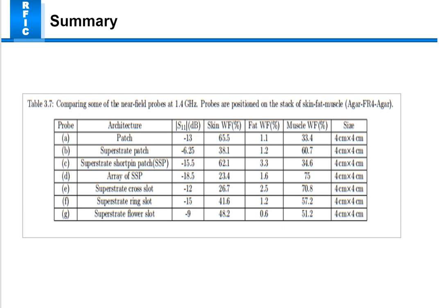And this probe was designed through simulation with a commercial full wave FEM simulator, HFSS, and volume power loss density in the tissue layers from the different probes are compared.